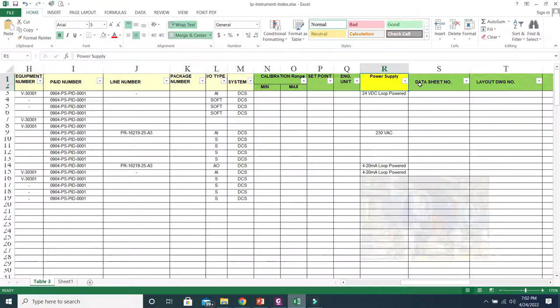Power supply, this information we also need to mention for any particular instrument which requires power supply. This is most important specifically for those instruments which require external power supply. So we can mention, just like a pressure transmitter, a 24 volt DC loop power supply. But Coriolis meter, magnetic flow meter, ultrasonic flow meter, these are the flow meters which use external power supply. So for those items we need to provide the specific power supply.